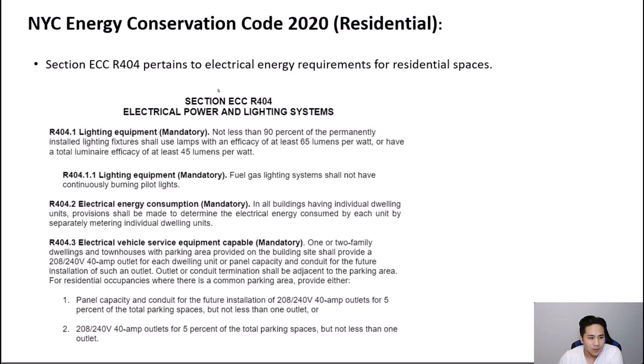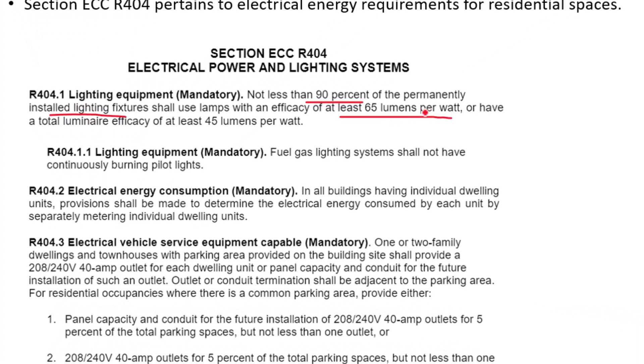The electrical requirements in the residential section of the energy code are a small section. For lighting, at least 90 percent of permanently installed light fixtures must use lamps with an efficacy of at least 65 lumens per watt, or the total luminaire efficacy must be at least 45 lumens per watt. This data is on the specification sheet for the light fixture — look up the model number to confirm it meets these requirements.